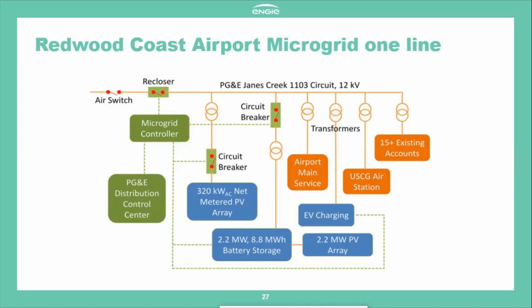But they also felt that some of the storage areas of the facilities on the airport, they could curtail load on and it would not have a significant impact. The other thing they looked at is rotating air conditioning, so they could cycle the time between when the air handlers turn on longer, increase the air temperature 2 to 4 degrees, and be able to curtail some of that load that way, where people could still operate and perform in those buildings, but it just wouldn't be as comfortable as it normally would. So these are some of the trade-offs in the design you have to make to figure this out. Okay, thanks.